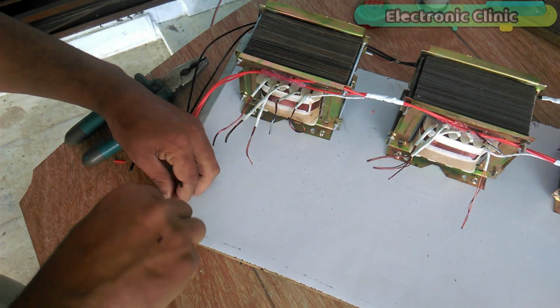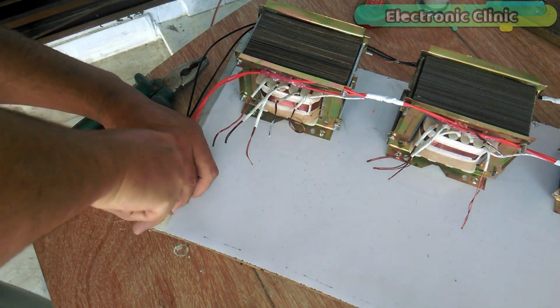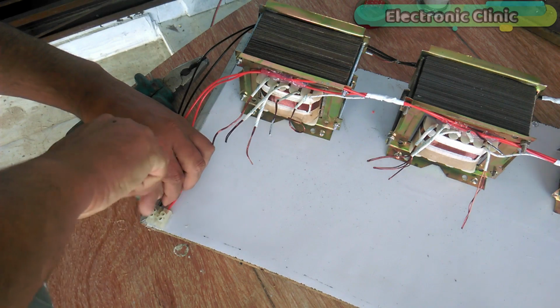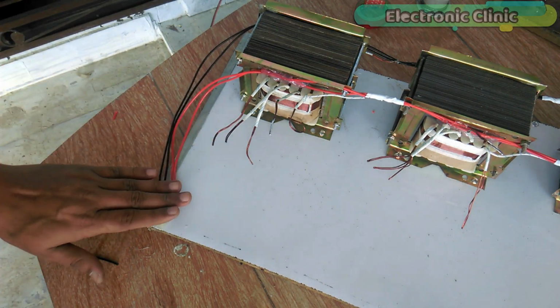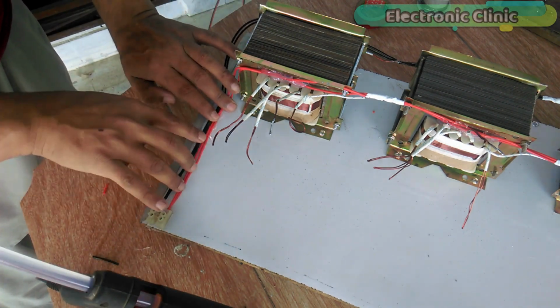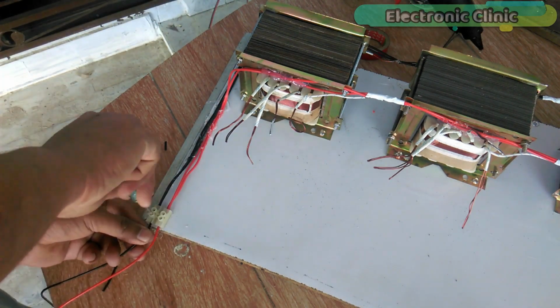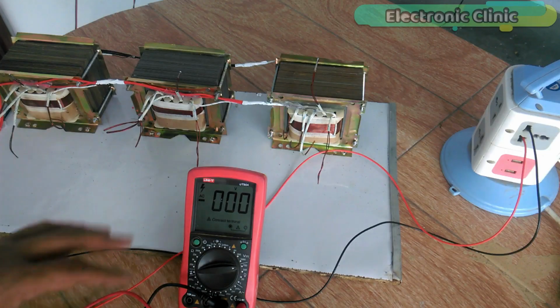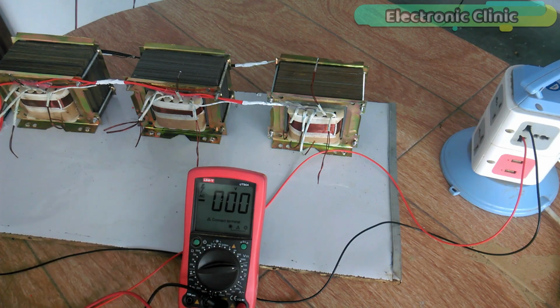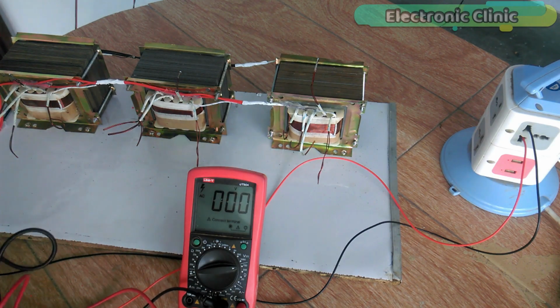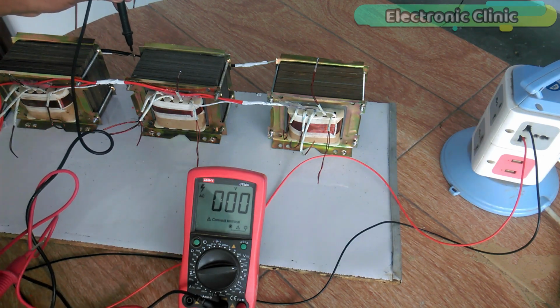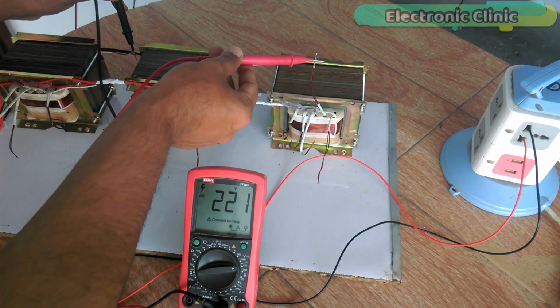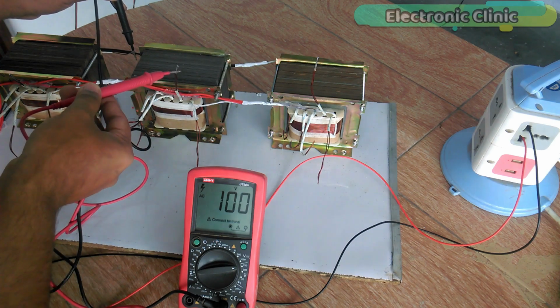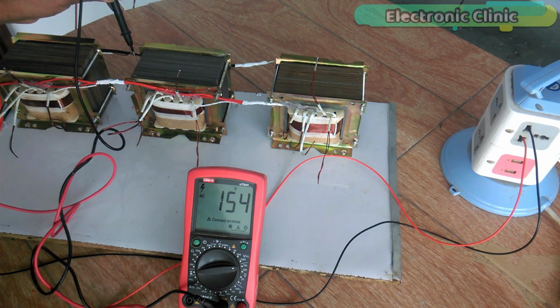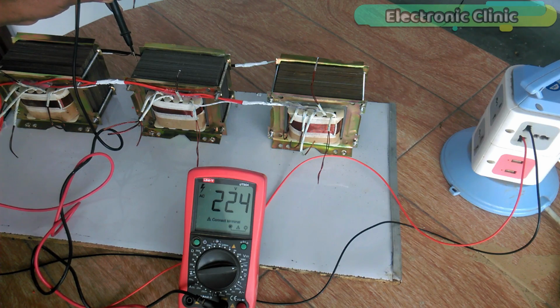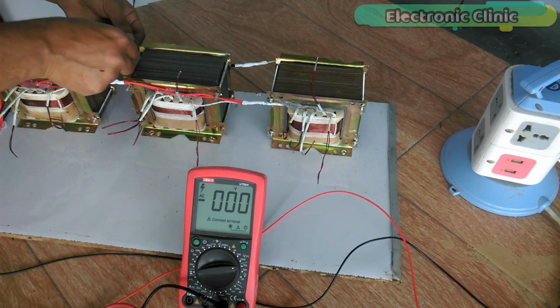Connect the live and neutral wires with the PVC strip connector. The meter is set on 750 volts AC. Do not touch these wires when the transformers are turned on. Connect one test lead with the neutral and connect the other test lead with the output. As you can see, all the three phases have 225 volts. We are done with the testing and all the transformers are working.